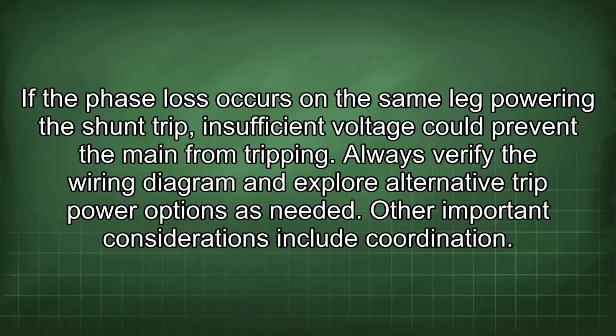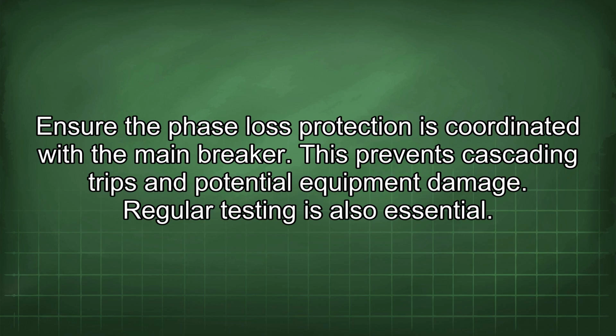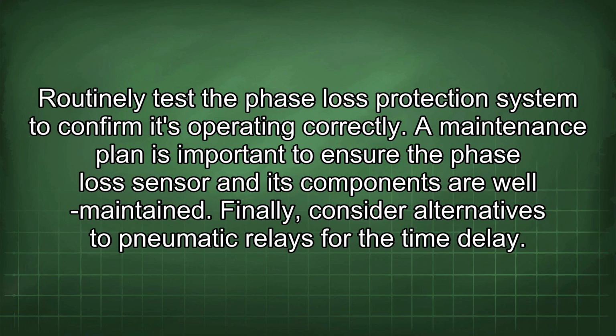Other important considerations include coordination. Ensure the phase loss protection is coordinated with the main breaker. This prevents cascading trips and potential equipment damage. Regular testing is also essential. Routinely test the phase loss protection system to confirm it's operating correctly. A maintenance plan is important to ensure the phase loss sensor and its components are well maintained.